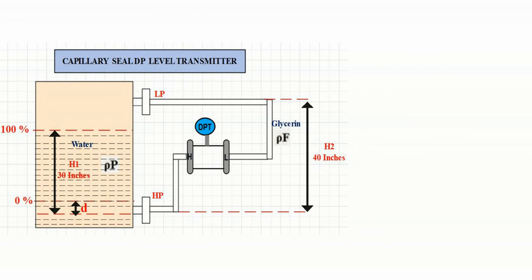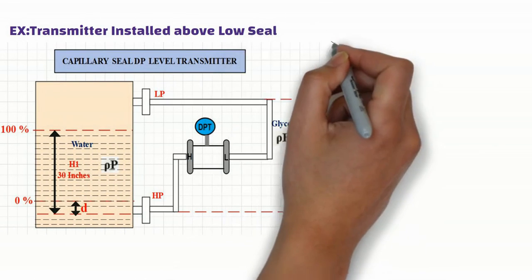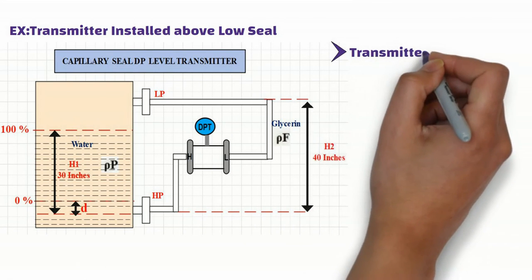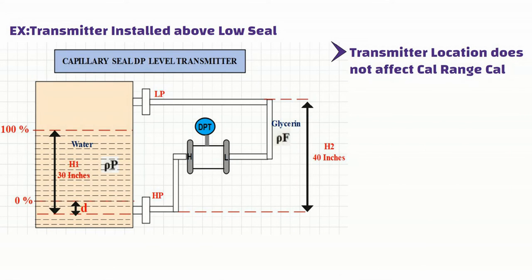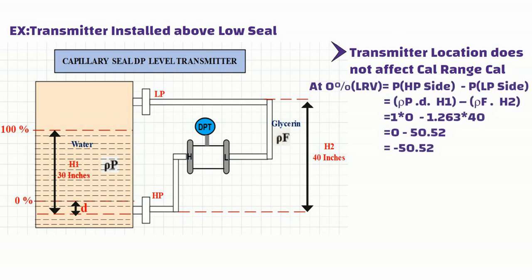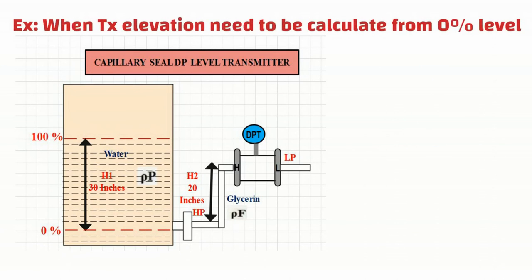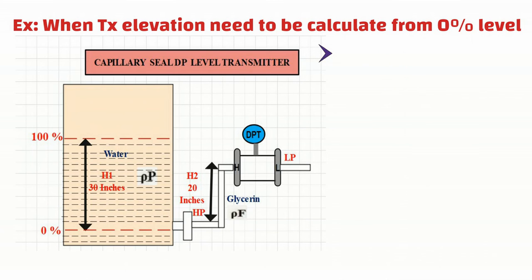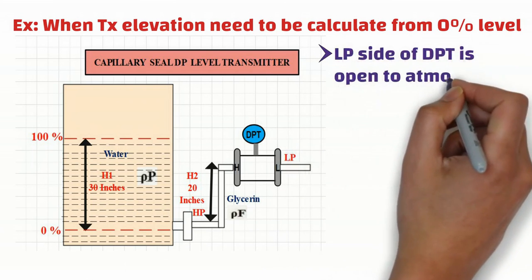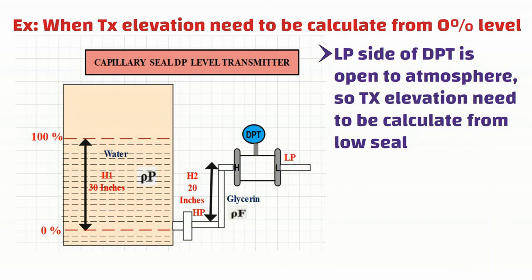As you can see, this is the example when the DP transmitter is installed above the low seal, and the 0% level is also above the low seal. However, as discussed earlier, transmitter location does not affect calibration range calculation when dual seals are used, so the LRV and URV remain the same as the previous example. However, the transmitter mounting elevation must be considered when one diaphragm is connected to the tank and the other diaphragm is open to atmosphere. In that case, we need to calculate the elevation of the transmitter from the low seal when calculating the calibration range.